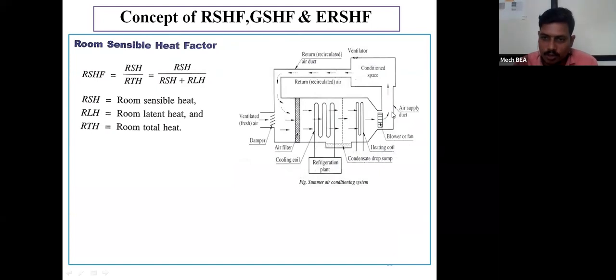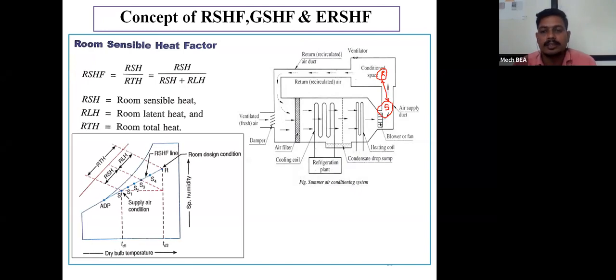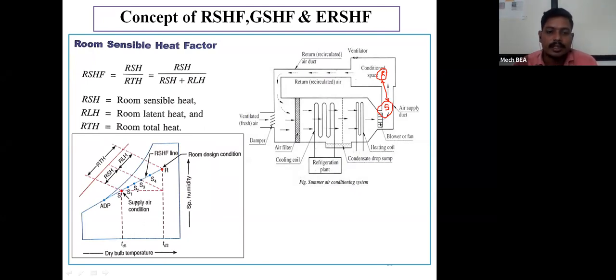If I want to represent the RSHF line on the psychrometric chart, the RSHF line is the line joining the condition of supply air and the required room condition. First of all, I should know the required room condition. If R is the required room condition and S is the condition of supply air, then the line joining them is called the RSHF line.